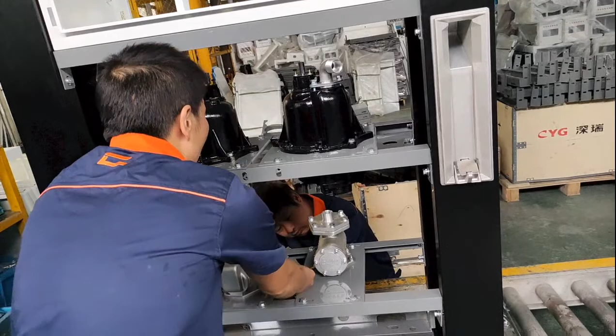If you use diesel, our engineer suggests cleaning the filter around every month. If diesel feels a bit dirty, clean it monthly too. If the gasoline or fuel is pure, you can just clean the filter around every 3 months. So I think the filter cleaning frequency depends on the media quality.